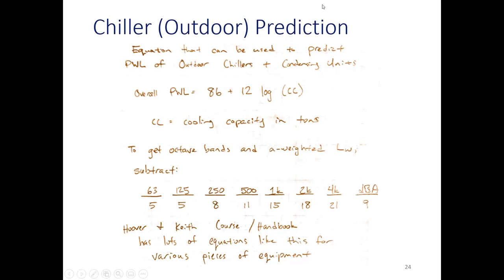Here we'll look at an example. I'll bring in a lot of what I've been talking about. An equation that can be used to predict the sound power level of outdoor chillers and condensing units is this equation right here. I mentioned Hoover and Keith; this is the equation that they give. It's 86 plus 12 log the cooling capacity in tons. Not a very complicated equation. You should probably put a red box around that. That'd be a useful one for you.